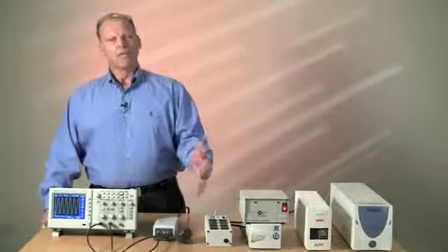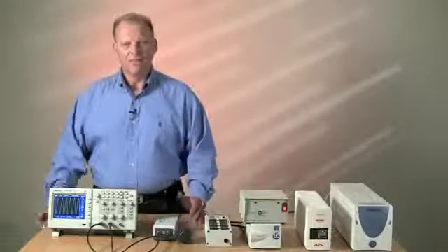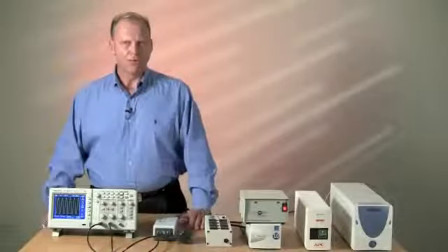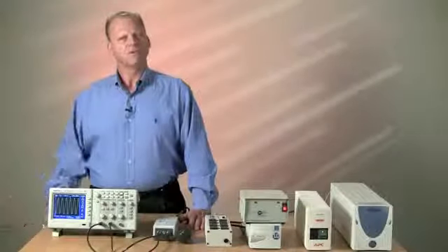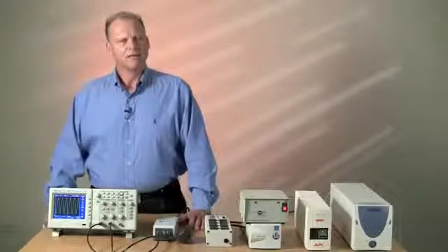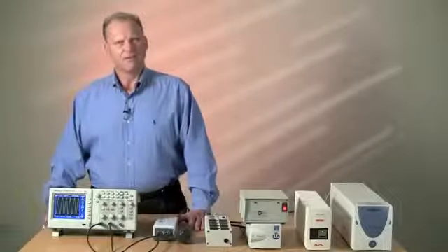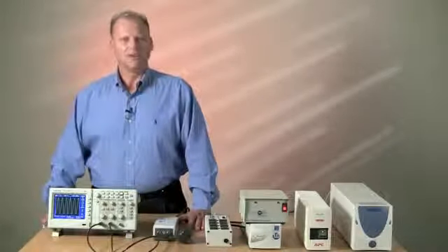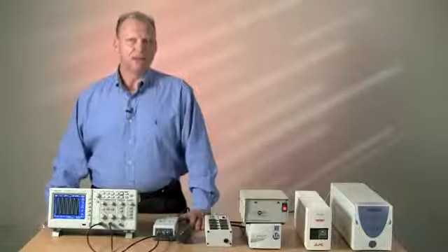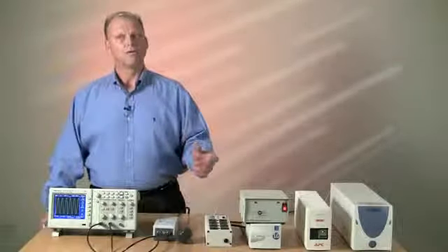So looking at worst case waveforms, like a lightning strike, what are acceptable levels for today's electronics? Semiconductor manufacturers will tell you acceptable noise between hot and neutral is 10 volts or less. With noise respect to ground, or common mode, you never want to see more than half a volt.